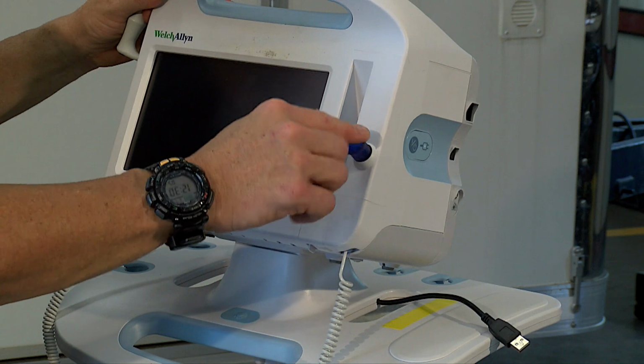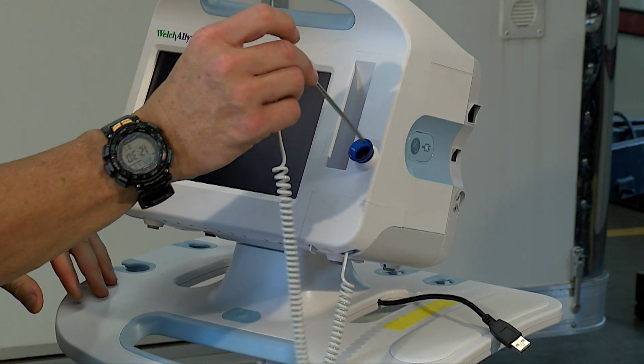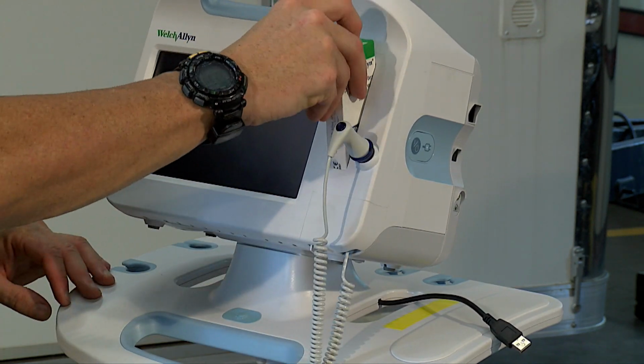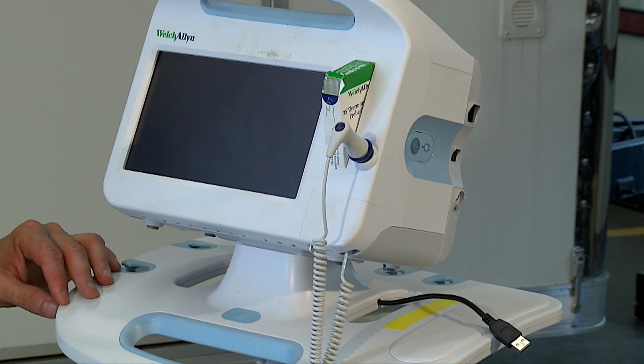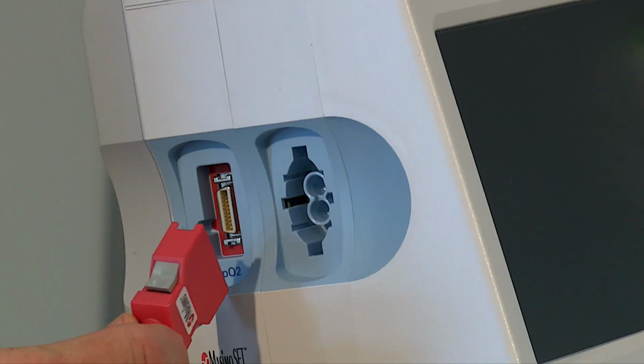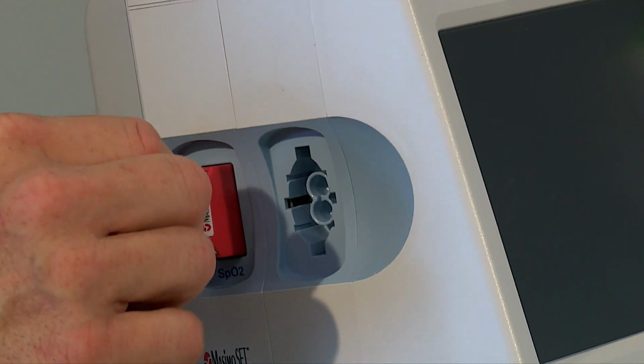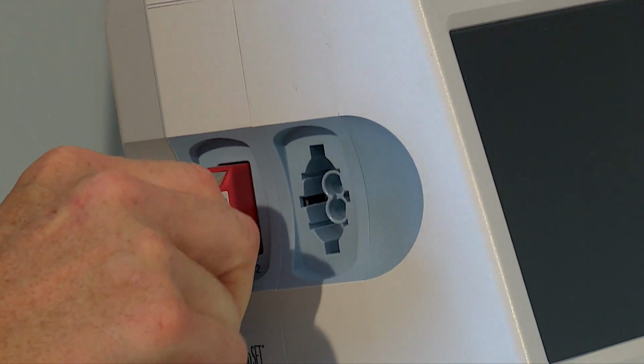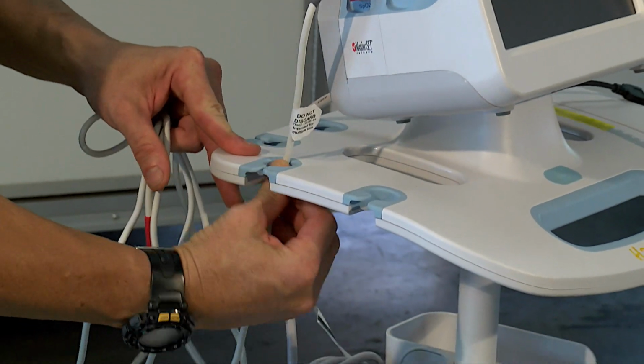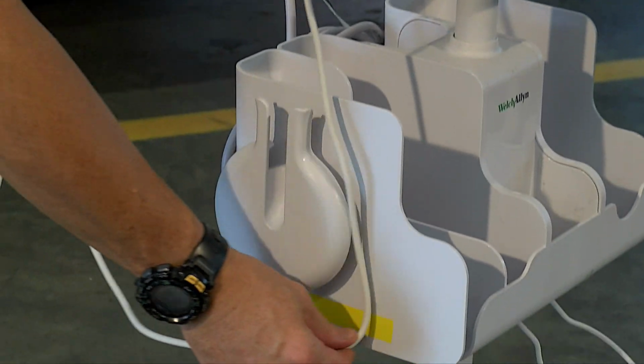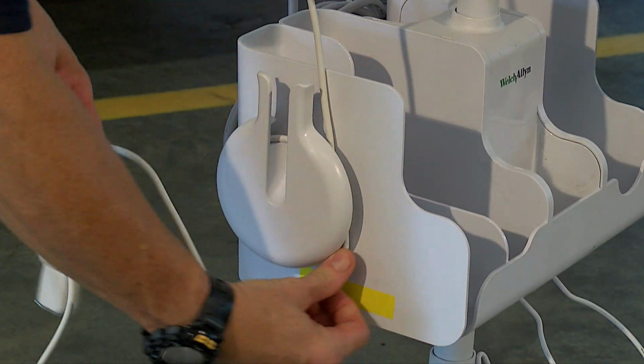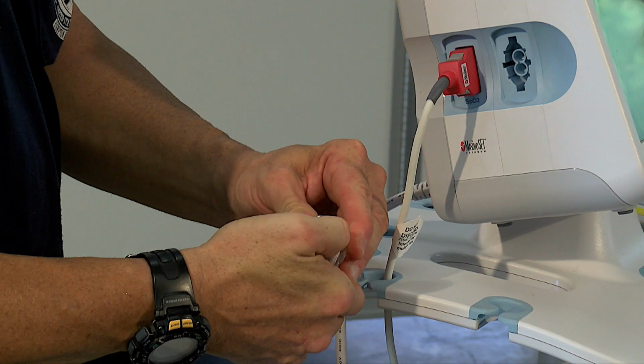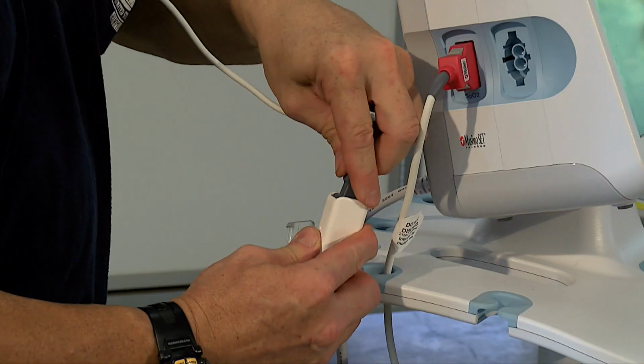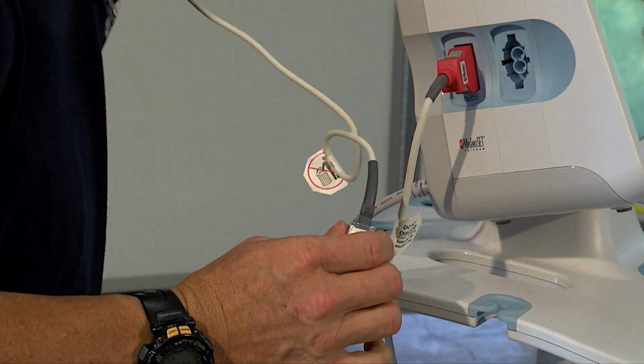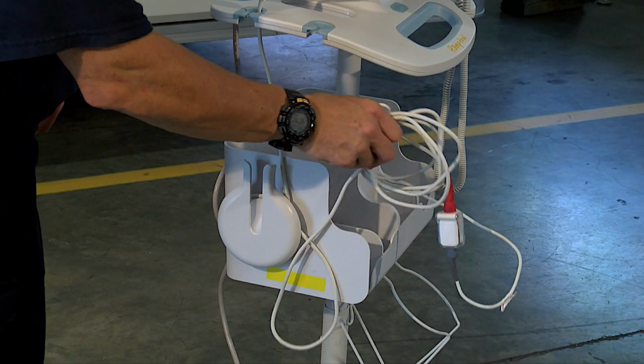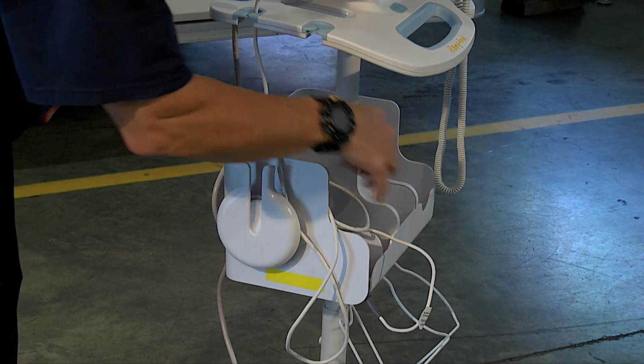Next, the probe sleeve is slid into place, and the temperature probe is placed into the sleeve. The box with the disposable probe covers is placed into the adjacent slot. The monitor's SPO2 cord is plugged into the marked slot on the left side of the monitor, and the extra cord should be placed around the SPO2 cleat. Next, plug the patient's end of the SPO2 cord to the monitor cord, locking the clear plastic cover into place. The extra cable can be placed in the side tray.